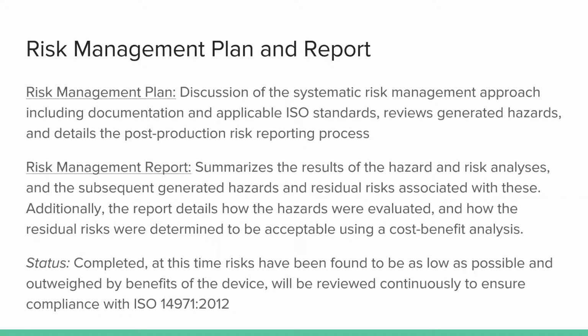So based on all of this information and following ISO 14971, the update from 2012, we developed a risk management plan and a risk management report. The risk management plan discusses our systematic risk management approach, including the documentation as well as applicable ISO standards that needed to be followed. It reviews the generated hazards from our device, so things that were caused based on risk controls that we put into place, and it details the post-production risk reporting processes, since the risk management process is continuously evolving and must be reevaluated even after the device is on the market.